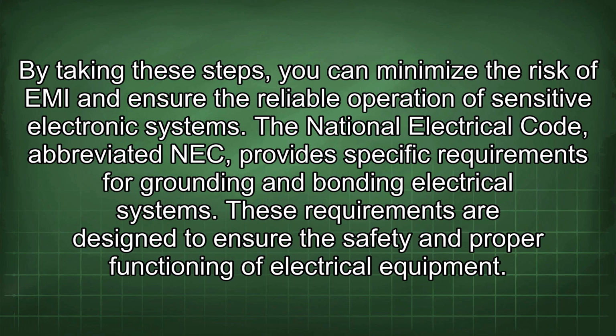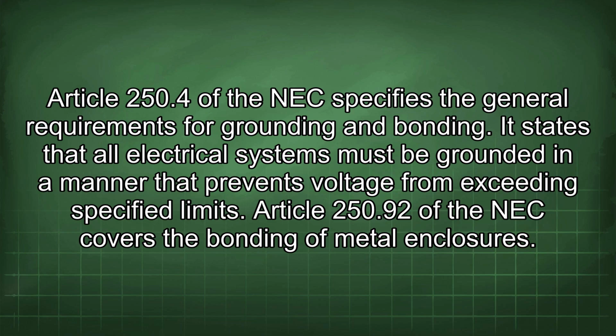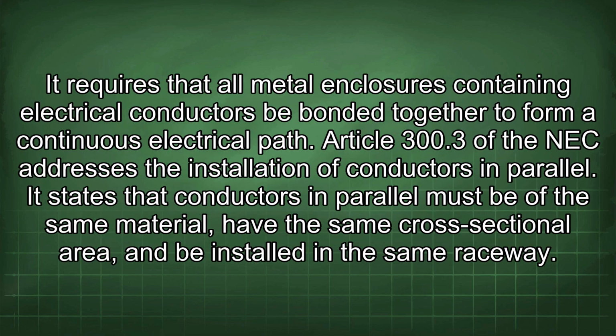sensitive electronic systems. The National Electrical Code, abbreviated NEC, provides specific requirements for grounding and bonding electrical systems. These requirements are designed to ensure the safety and proper functioning of electrical equipment. Article 250.4 of the NEC specifies the general requirements for grounding and bonding. It states that all electrical systems must be grounded in a manner that prevents voltage from exceeding specified limits. Article 250.92 of the NEC covers the bonding of metal enclosures. It requires that all metal enclosures containing electrical conductors be bonded together to form a continuous electrical path.